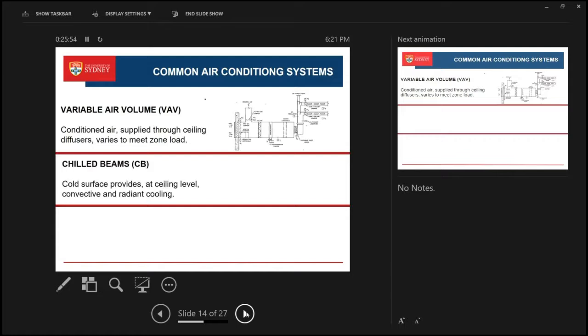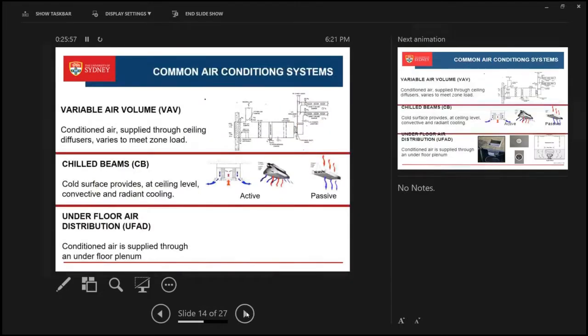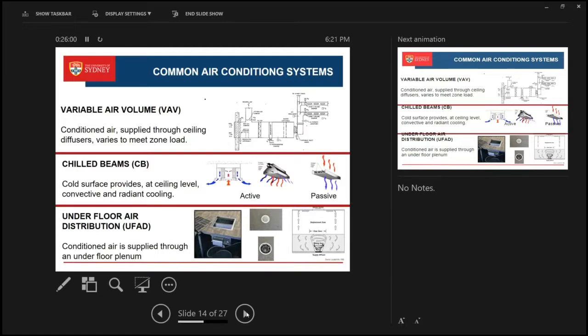What I'm going to talk about now is different artificial environments, namely variable air volume—the air conditioning system where the air volume varies in response to demand. If there's a certain number of people, the VAV system will work out and use more air. The thermostat will say, if conditions aren't maintained, increase the volume. But by the same token, if there are very few people, the thermostat will say we're satisfied, so shut down or throttle down the air—hence the name variable air volume. Chilled beams, I think everybody is now quite familiar with.